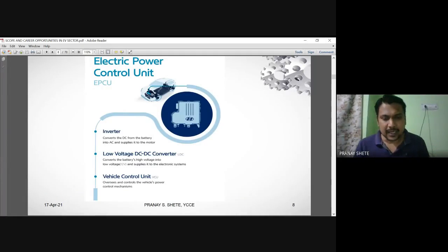In the electric power control unit, that is EPCU, there are 3 elements. One is the inverter, which converts the DC from the battery into AC and supplies it to the motor. This is the basic purpose of the inverter - the energy storage in the battery is in DC form, and you need to convert this DC into AC with a specified voltage and frequency.